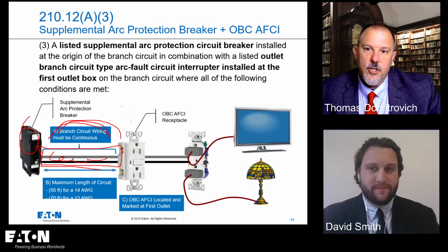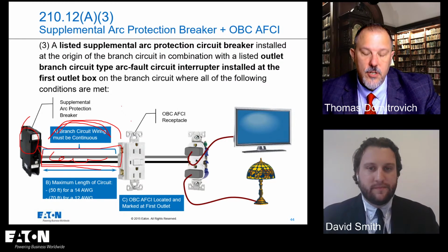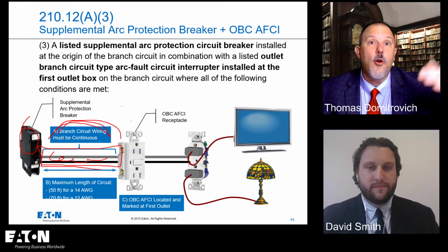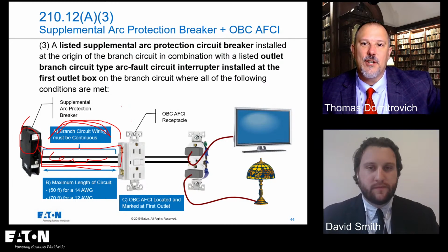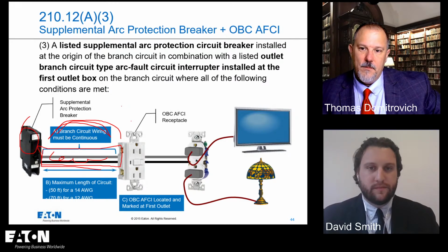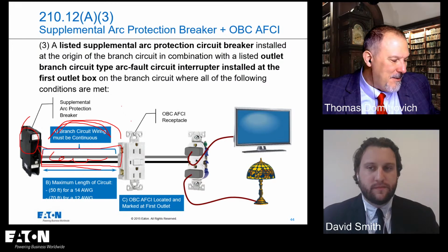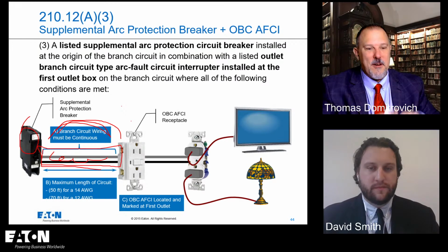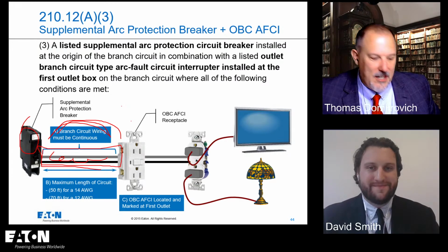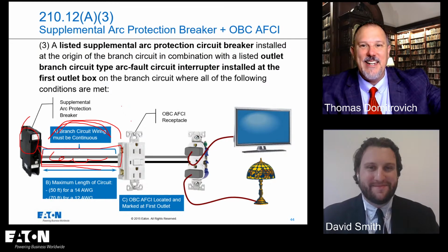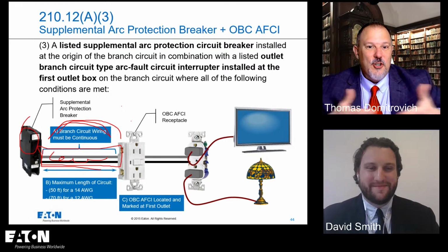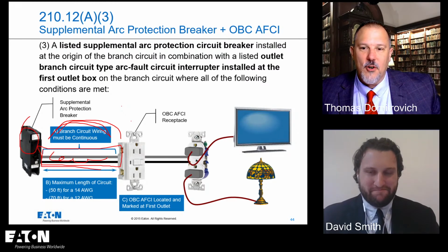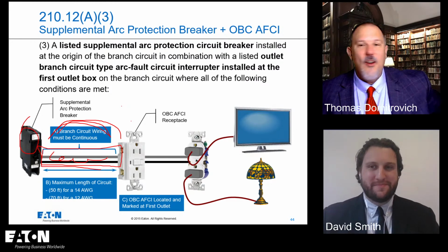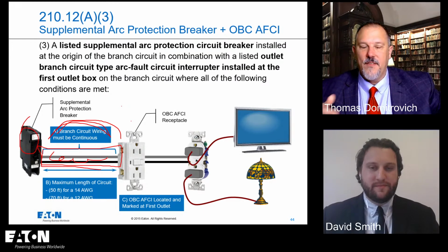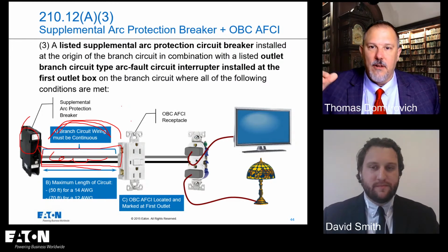We did research. The Wiring Device Manufacturers Consortium did research to find out what are the available fault currents at service panel boards for residential homes. And then the ACBMA, the American Circuit Breaker Manufacturers, went out and said, well, we're going to do studies too. Well, they all brought data to the table, and you're like, well, this is really great because you're getting a good cross-section of what fault currents are across the United States. And obviously, the wiring device guys brought stuff that said, hey, the fault currents are like 1,000 amps.